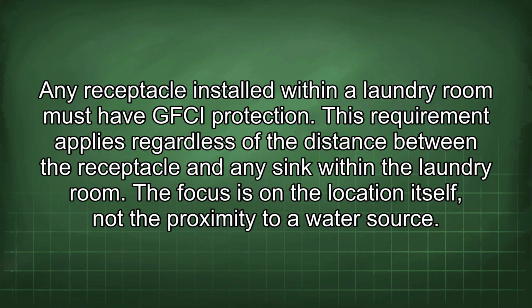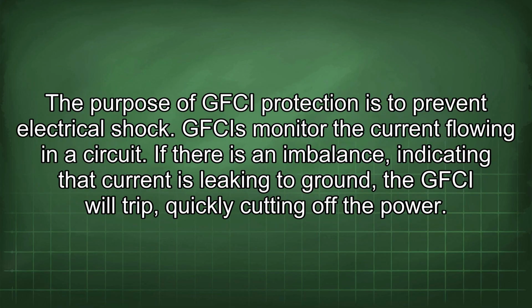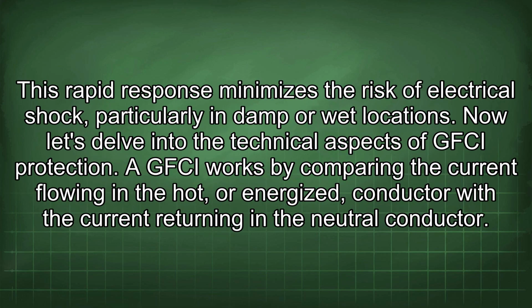Any receptacle installed within a laundry room must have GFCI protection. This requirement applies regardless of the distance between the receptacle and any sink within the laundry room. The focus is on the location itself, not the proximity to a water source. The purpose of GFCI protection is to prevent electrical shock. GFCIs monitor the current flowing in a circuit. If there is an imbalance, indicating that current is leaking to ground, the GFCI will trip, quickly cutting off the power. This rapid response minimizes the risk of electrical shock, particularly in damp or wet locations.